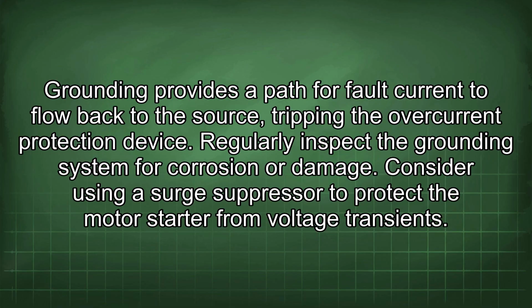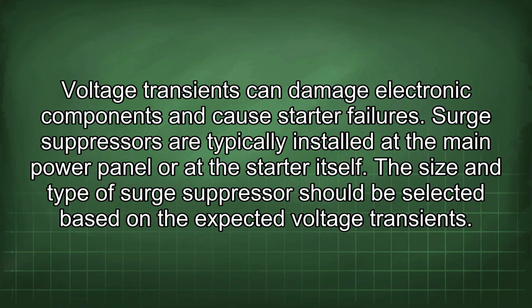Consider using a surge suppressor to protect the motor starter from voltage transients. Voltage transients can damage electronic components and cause starter failures. Surge suppressors are typically installed at the main power panel or at the starter itself. The size and type of surge suppressor should be selected based on the expected voltage transients.